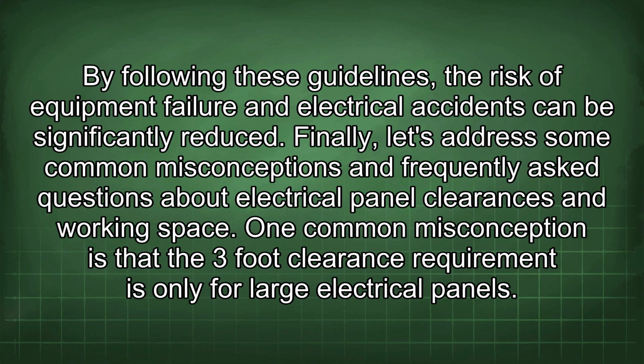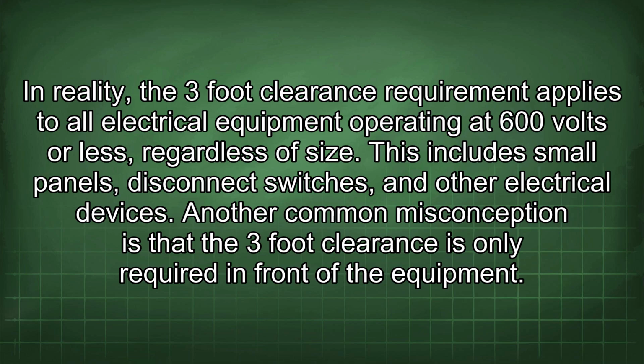Finally, let's address some common misconceptions and frequently asked questions about electrical panel clearances and working space. One common misconception is that the 3-foot clearance requirement is only for large electrical panels. In reality, the 3-foot clearance requirement applies to all electrical equipment operating at 600 volts or less, regardless of size. This includes small panels, disconnect switches, and other electrical devices.